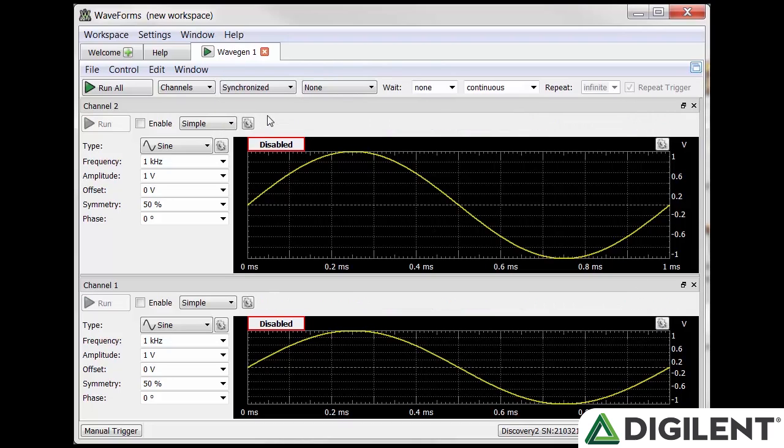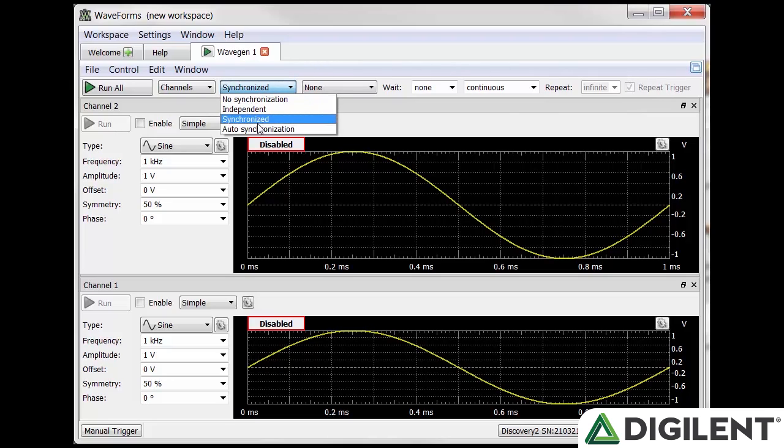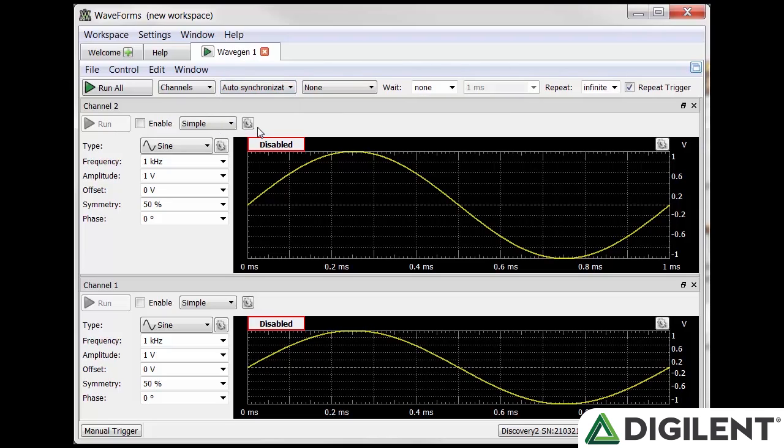In synchronized mode, the trigger, wait, run, and repeat settings are all the same for all selected channels within the same instrument instance. The auto synchronization mode is similar to the synchronized mode, where runtime is automatically adjusted to the longest period from all channel settings.